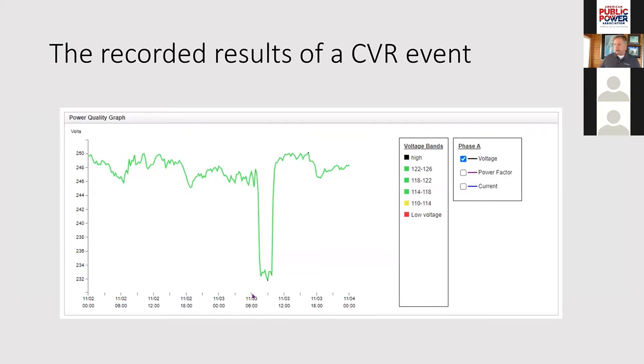On November 3rd, 2020, we scheduled an event in the morning. You can see this huge drop where we changed the set point voltage at the substation regulators. It rode through at the bottom for a period of time, then the event ended and voltage came back up to a normal range.